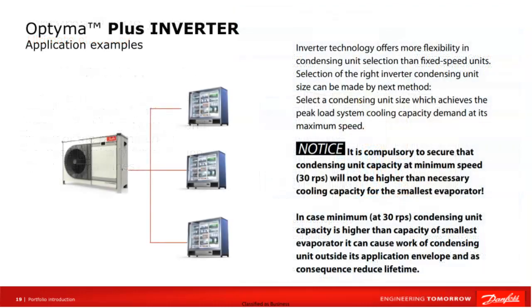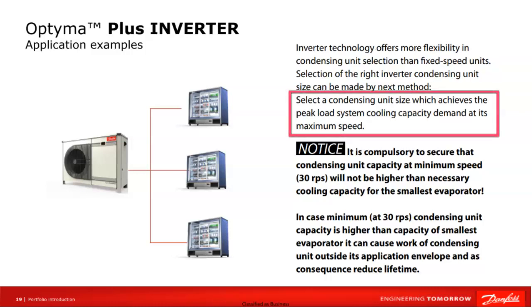Condensing units equipped with inverters provide more flexibility in selection than fixed-speed units. Selecting the right inverter condensing unit can be done using the following methods. Select a condensing unit size that achieves the desired peak load cooling capacity at a maximum speed.